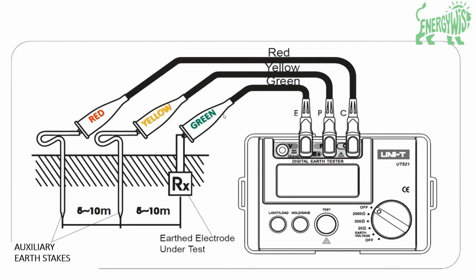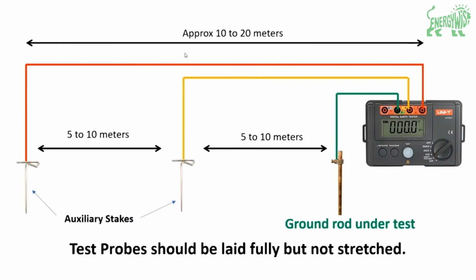To proceed, we connect in this way. The green lead connects to the ground rod at terminal E, and terminal P connects with the yellow lead, which goes to the earth auxiliary spike at a 5 to 10 meter distance from the green one. Then we connect the red in this way. If we connect it at a 5 meter distance, the red to the green will be 10 meters, but if we connect it at a 10 meter distance, it should be 20 meters. It's better not to tie the wires together when we connect them in this way.